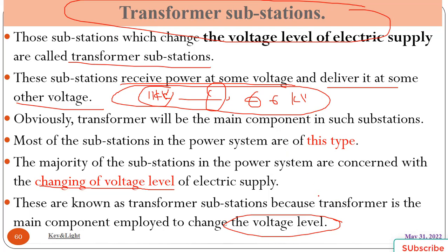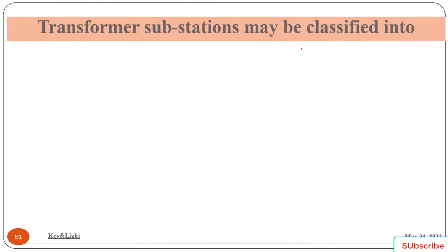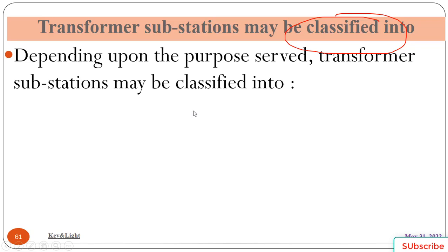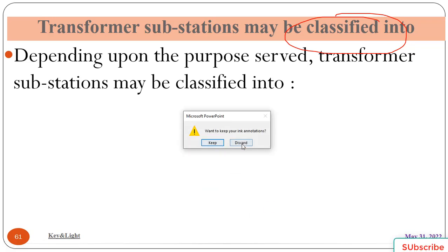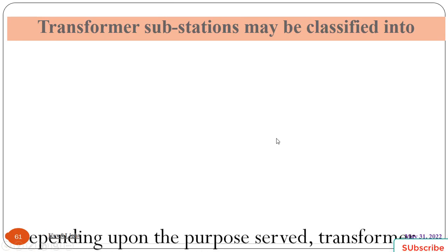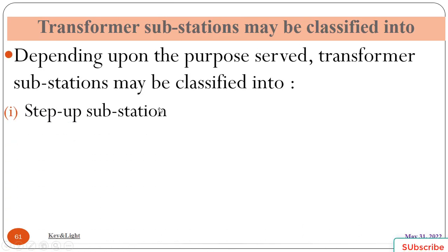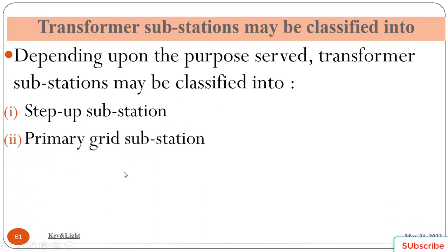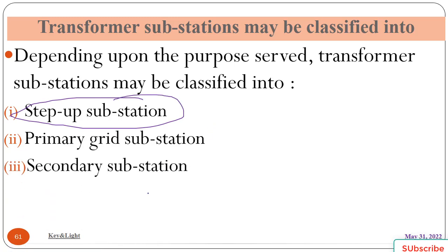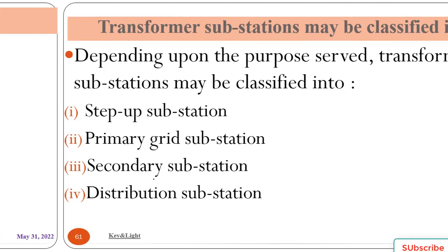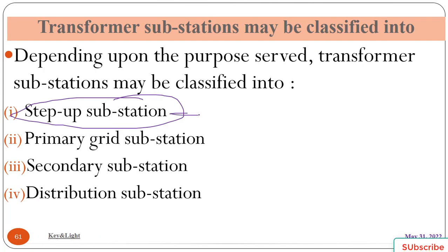As we said, the main task of a transformer substation is changing the voltage level, either maximum or minimum level of the given amount. Second, depending upon the purpose served, transformer substations may be classified into step up, step down, primary grid, and secondary grid substations. The other one is distribution substation.